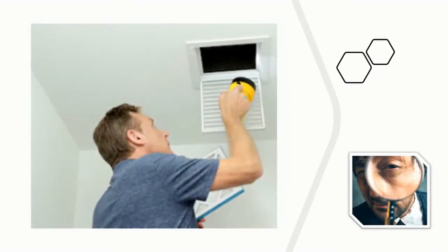If the system is being installed in an existing home, ensure the contractor does a duct evaluation. It can be done by counting the registers and looking at the accessible ductwork to ensure it's not undersized, and that good duct practices such as taper takeoffs, radius elbows, and turning vanes are used.